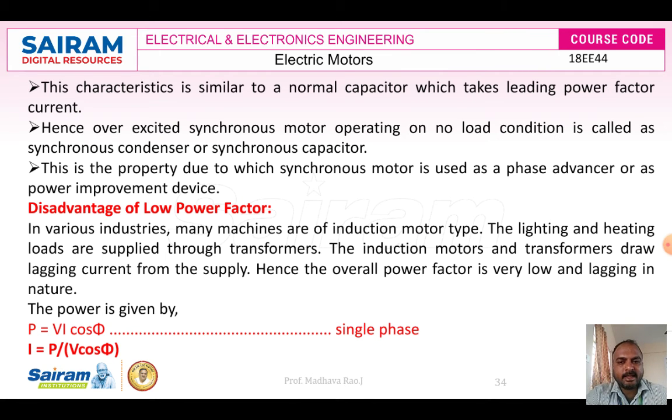Its characteristics are similar to a normal capacitor. A synchronous condenser we can take as a capacitor, which takes a leading power factor current. When the over excited synchronous motor operates under no load condition, it is called a synchronous condenser or synchronous capacitor. This is the property due to which the synchronous motor is used as a phase advancer or power factor improvement device.